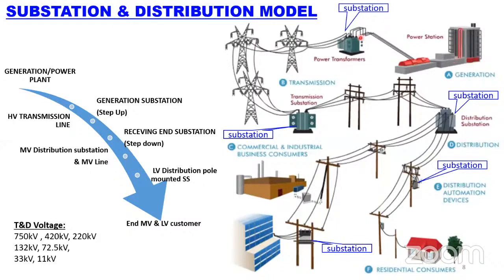So now if you look at this overall map, you can see there is a substation closer to the power generation, number 1. Number 2, the receiving station. Number 3, the distribution substation, which converts into medium voltage. Then after that, there is a substation we call the pole mounted substation on the distribution pole. This is the industrial customer. This is also a distribution pole mounted transformer. This is also a distribution pole mounted transformer.